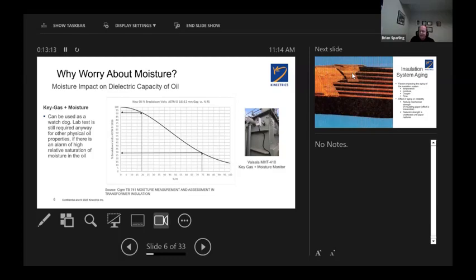That's quite important. And like Chris was mentioning before, when we want to get this data and trend the data over time, there are ways to monitor the moisture in the oil of a transformer, moisture sensors, and the temperature associated with it, to be able to follow this movement of the water in and out.